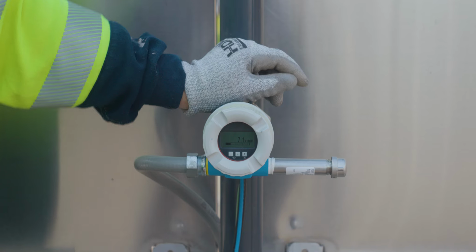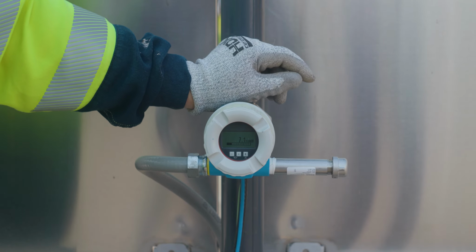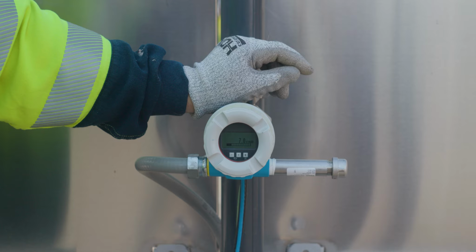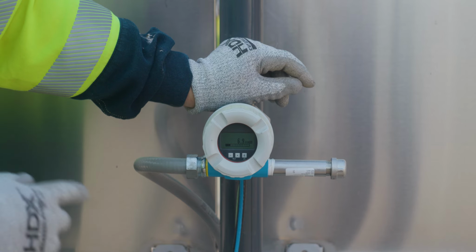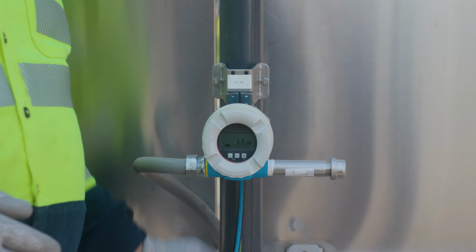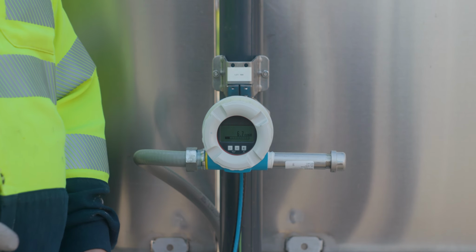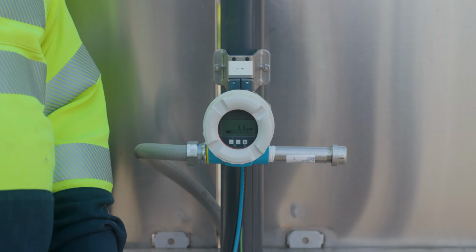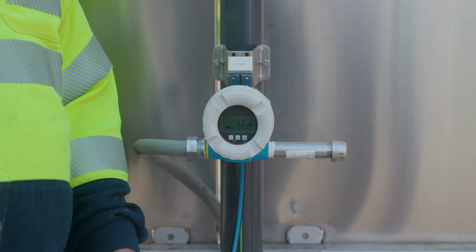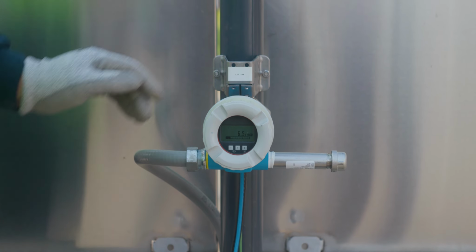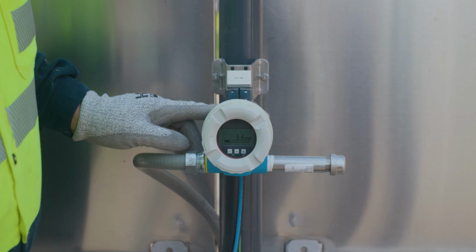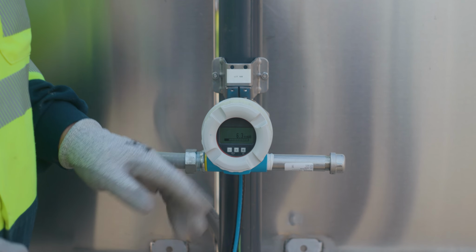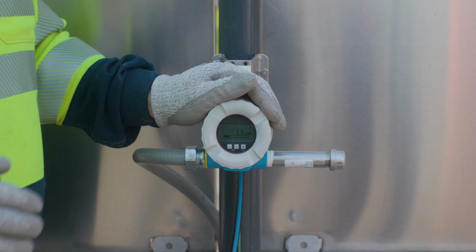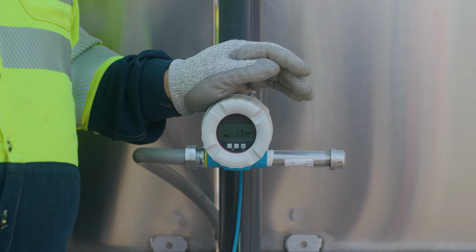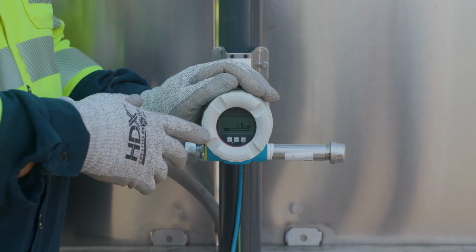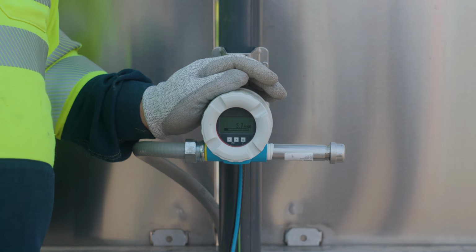We're at the level transmitter, which is the PLC's primary means for turning the pumps on and off at the prescribed levels. So it uses this device with a sealed connected cable going down to a pressure transmitter. That pressure transmitter senses the weight of the water or the pressure above the sensor, and then that pressure is converted to a 4 to 20 signal, and then you can use the settings on these buttons here to scale it. It's scaled based on the level and the controls that they're going to use in the PLC. And whatever scale that's in here has to match the scale in the PLC or vice versa.